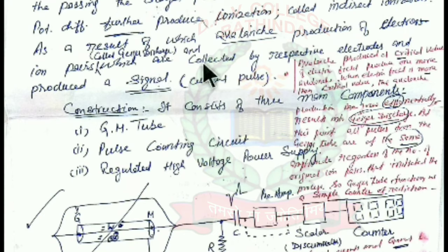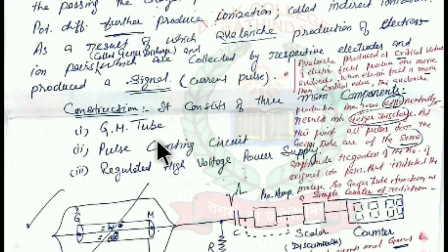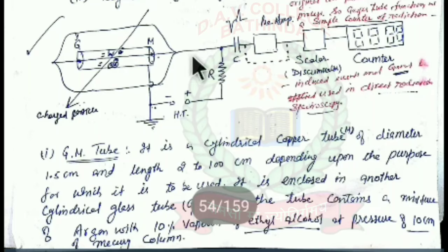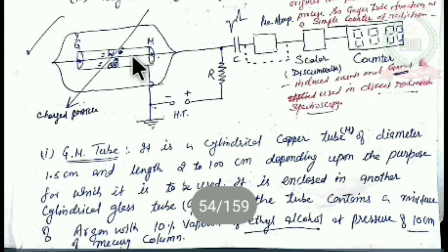These electron-ion pairs are collected by their respective electrodes and produce a signal, that is, a current pulse. The GM counter basically consists of three parts: the GM tube, the pulse counting circuit, and the regulated high-voltage power supply. The GM tube is encapsulated in a glass tube, and internally it contains a central wire which is the anode, and a cathode cylinder.